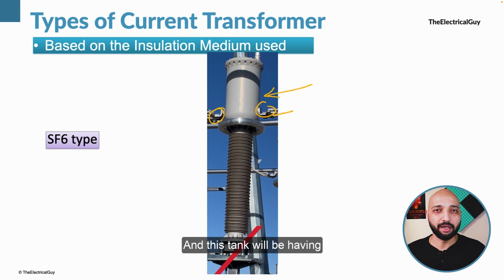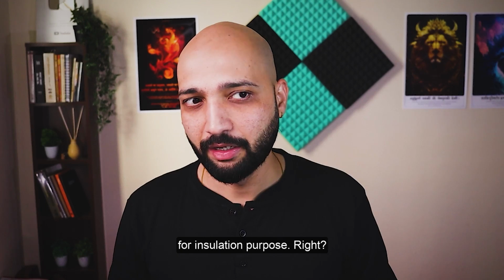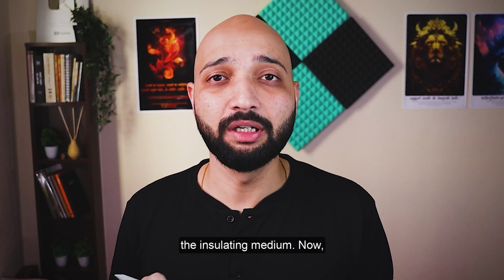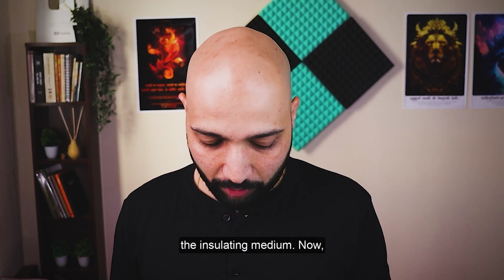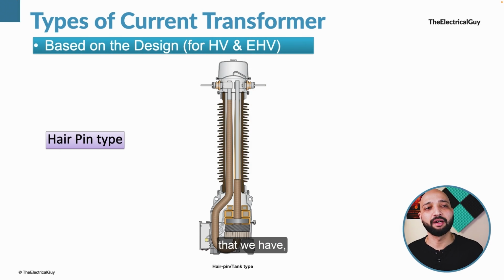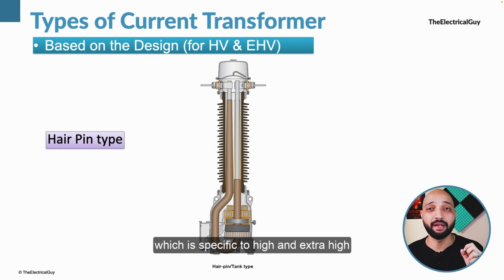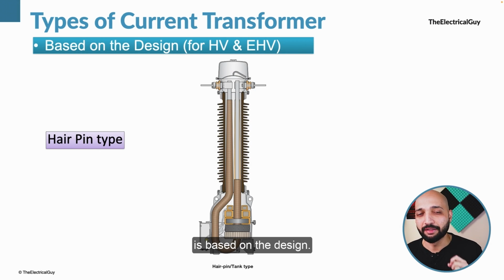And this tank will have secondary cores, and it is filled with SF6 gas for insulation purposes, right? So that is the types based on the insulating medium. Now moving on to the third category, which is specific to high and extra high voltage current transformers, that is based on the design.